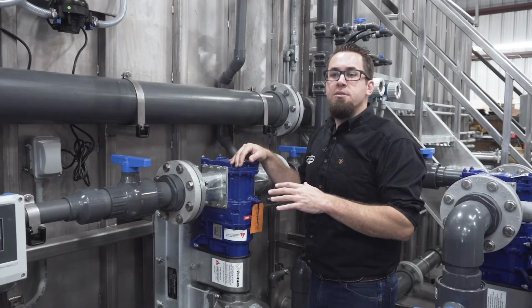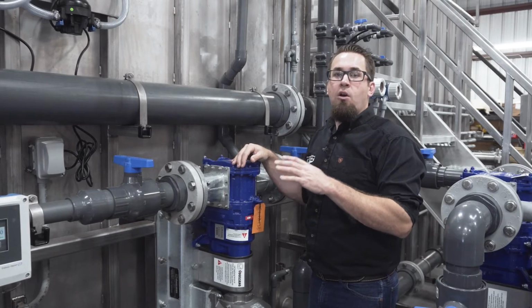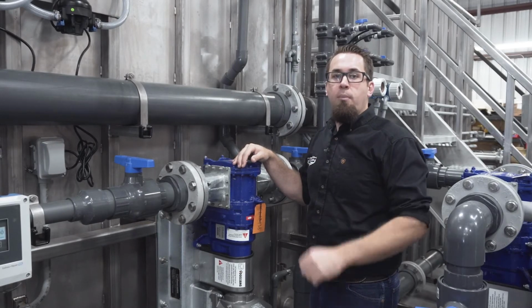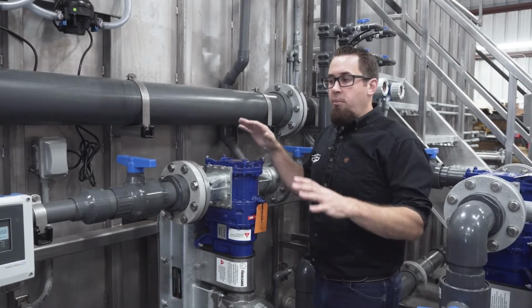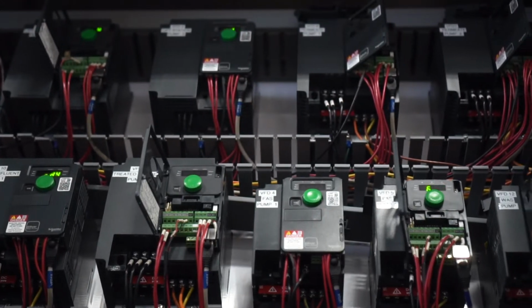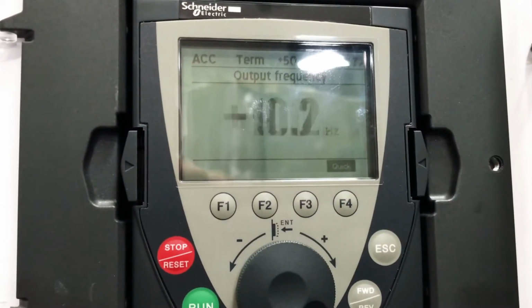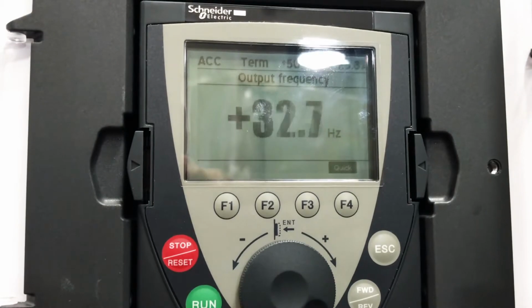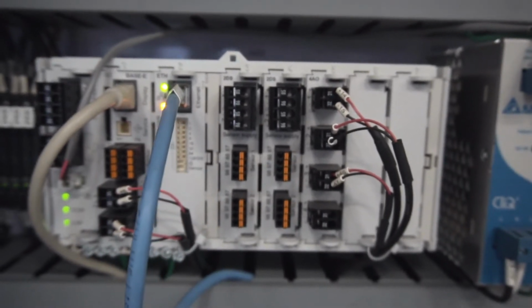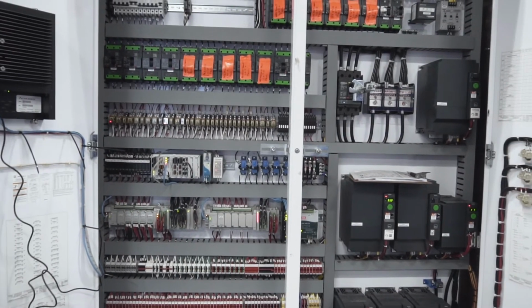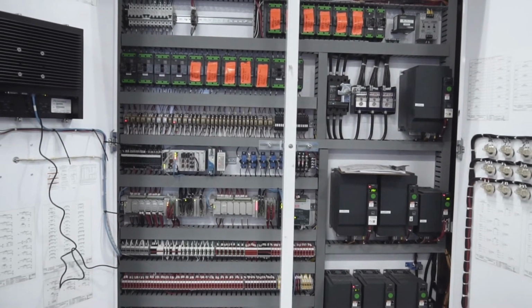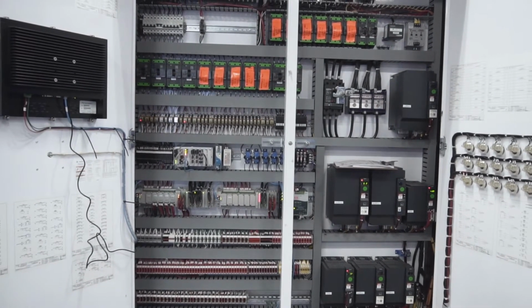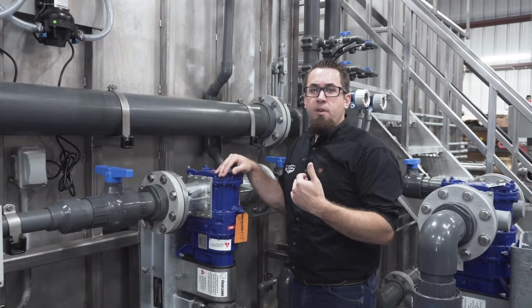I want to talk about some of the features that we design into all of our treatment systems to make it so that you cannot harm the membranes, and it protects you as the operator and maintenance technician from ever damaging the membranes themselves. Let's talk about some of those features. The first is the fact that all of these permeate pumps are on a VFD with very strict ramp up and ramp down guidelines. And then the PLC itself reads in milliseconds and allows instantaneous stops in the event that it ever sees a spike in the TMP, whether that's on the positive or negative side.